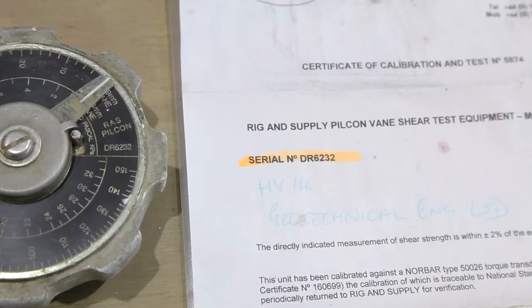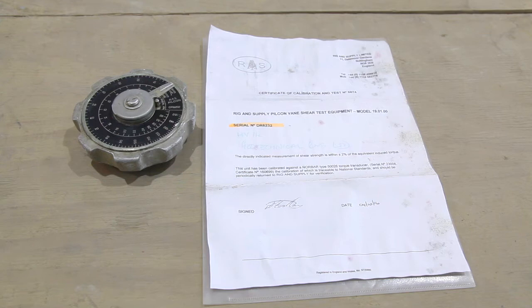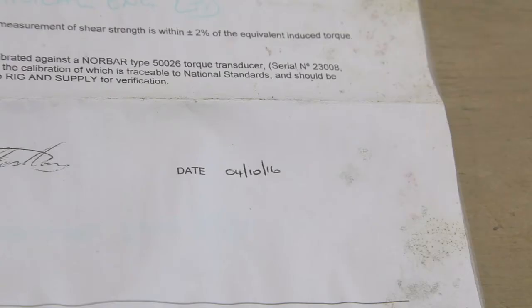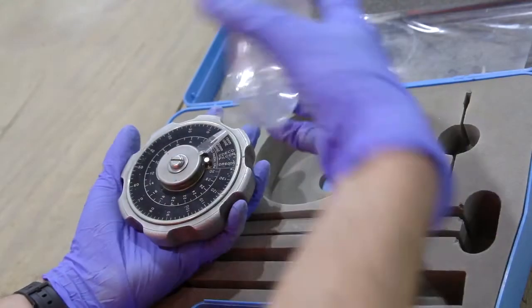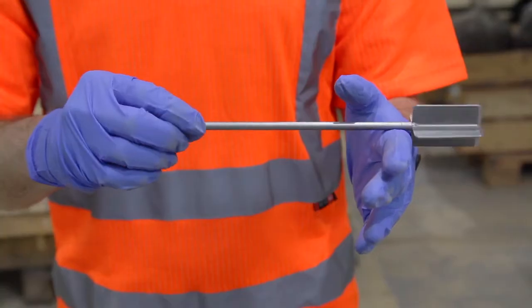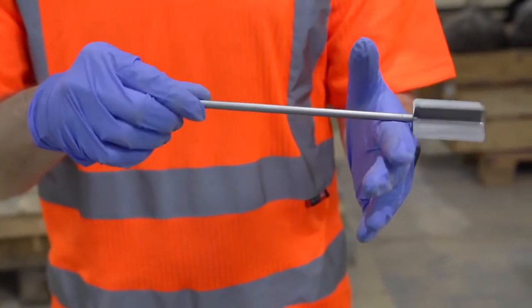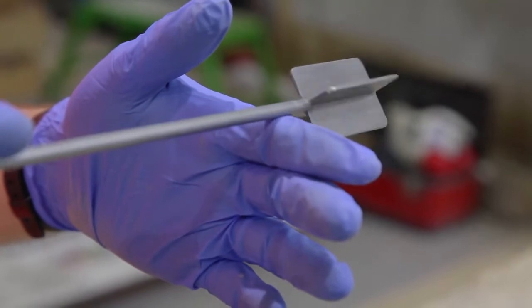Our vanes are calibrated each year. Check that a valid certificate is provided with the vane. Remove the cover. Check for bent rods and a clear mechanism. Do not use the instrument if damaged.